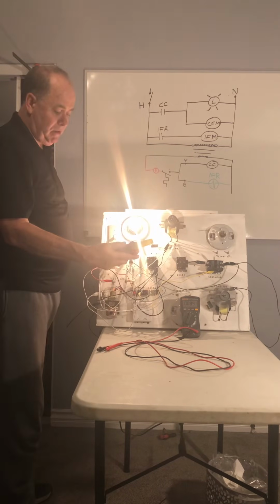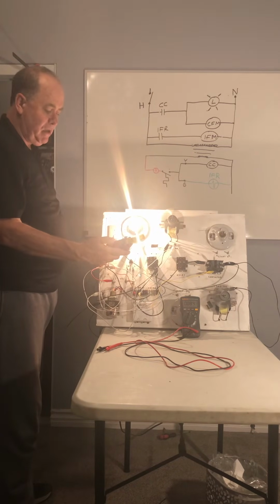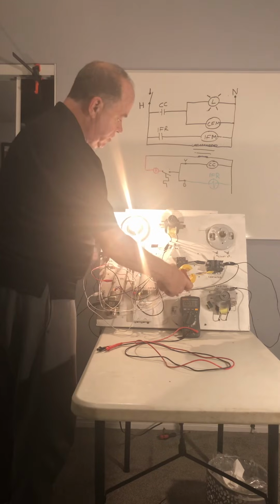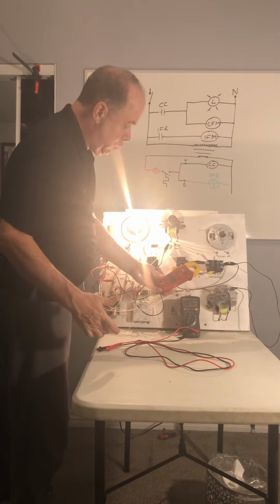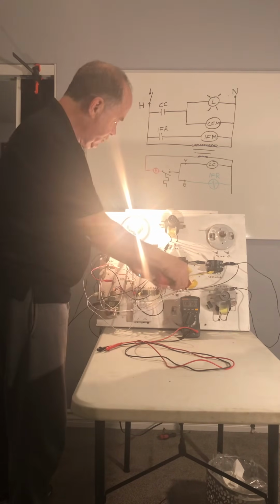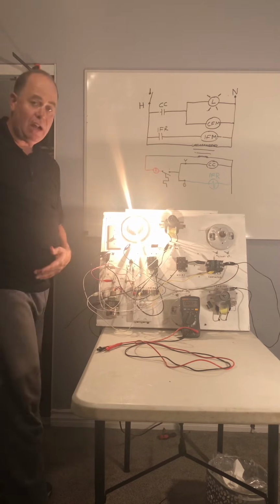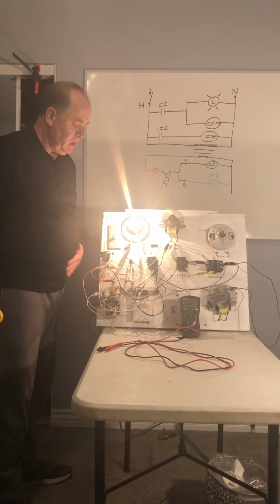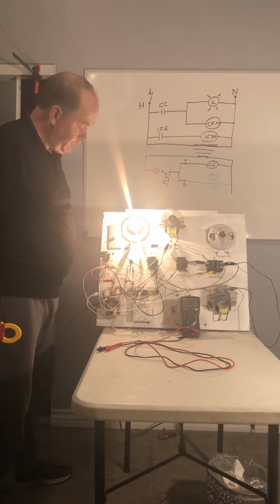Let's try and go ahead and take a reading. I'd be shocked even if we're getting 1/10 of an amp. It probably won't even register much on our ammeter, 0.1 amps. And certainly the contacts can handle that on the thermostat.